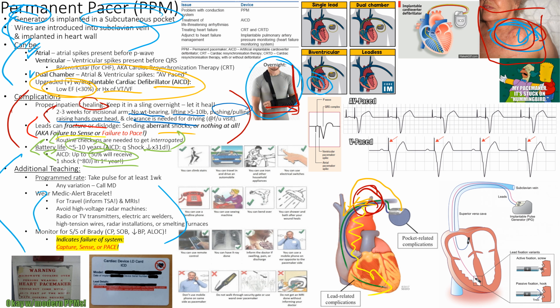So we can call the manufacturer. At both hospitals we have a pacemaker interrogation kit where they can figure out what's going on with their pacemaker, for example for Boston Scientific pacemakers, right? So the programmed rate should be set at maybe 60 or 50, depending on what the cardiologist says, and they'll tell them to take their pulse for about a week. Make sure that your heart rate is actually 50 or 60. That means the pacemaker is working. If the heart rate's 40 and the pacemaker is set to 60, that means the pacemaker is not working.